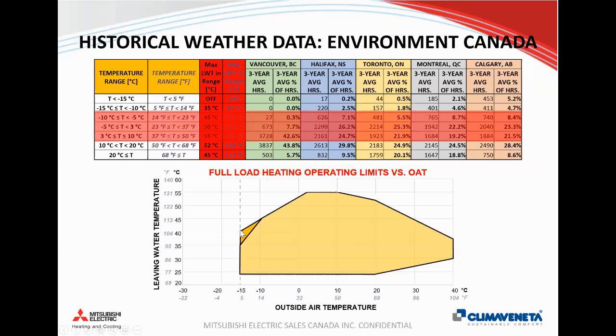The reason why in the previous slides I was talking about -10 is because this is a common design point in Vancouver, where at -10 degrees Celsius outside air temperature, typically from these types of heat pumps, you can still achieve a 45 degrees Celsius supply. So although the cutout is -15, maybe you don't want to operate it below -10 anyway, because for convection heat emitters, 35 degrees is probably too cold to get useful heat transfer into the building. But even if you just look at the amount of hours that we went over in the last slides, where it was between -10 and -5, you'll see that you can get different supply temperatures.